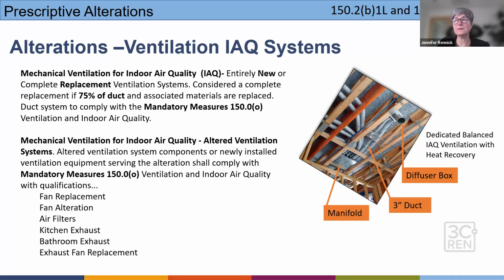When we talk about these balanced IAQ ventilation systems with either heat recovery or energy recovery, often what we're talking about is having a small ducted system run throughout the house. There's also through-the-wall ventilation type systems, but typically we're talking about a ducted system. Depending on how large of a project you're working on, it could be that you have the main ERV or HRV core in one location, like a closet, and then from there it would duct out to a manifold, and then a bunch of 3-inch ducts running into various rooms, bringing in fresh air, and also pulling the stale air out at other points.